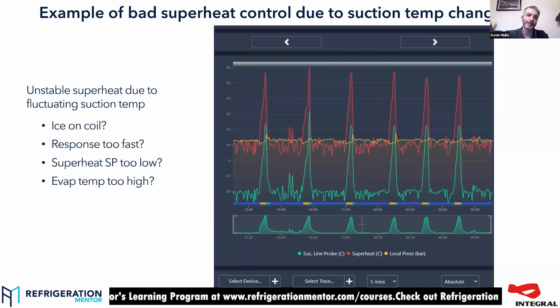There's no air flowing through that bit. So even though the rest of the coil is working just fine, that top bit will flood liquid into the suction because there's nothing being evaporated in that section. And you see that a lot. So, as we see on this slide here, bad superheat control due to suction temperature changing.